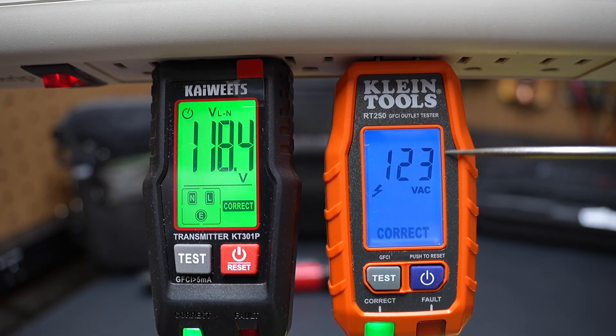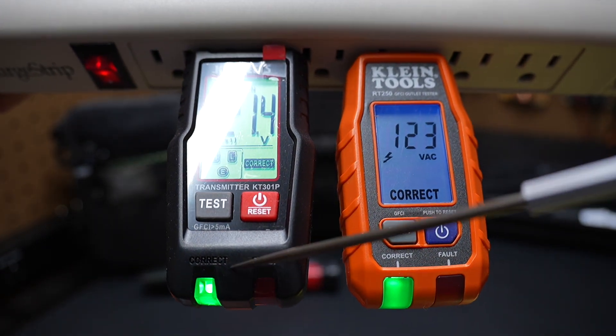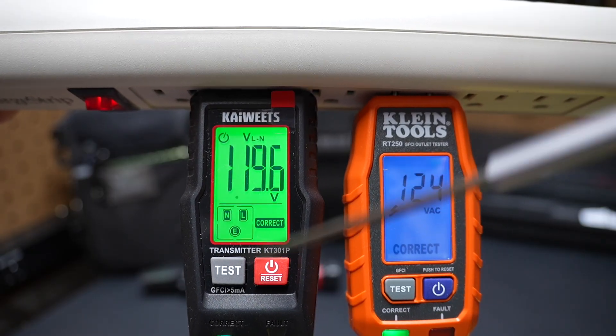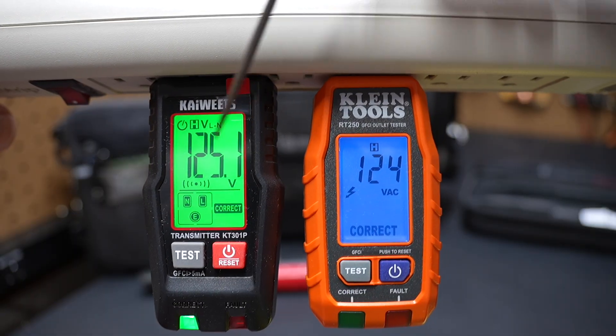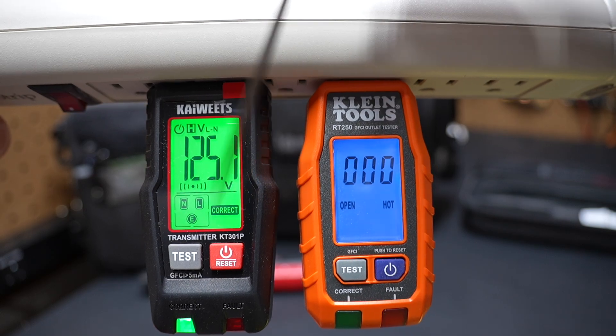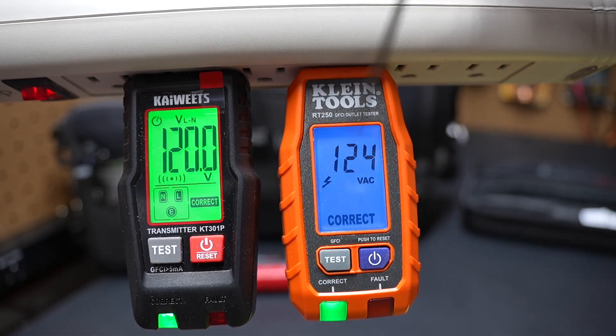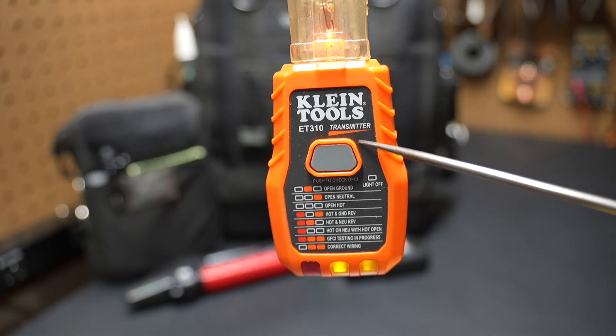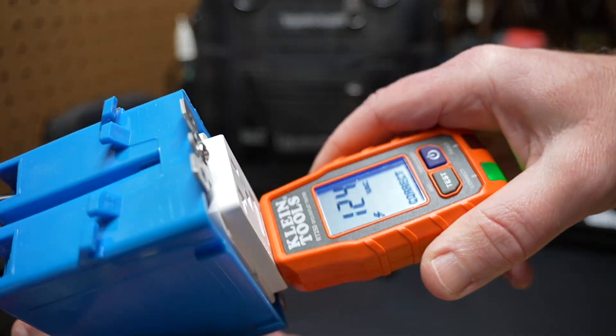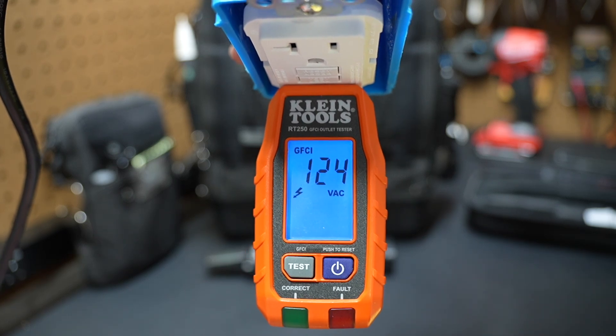Let's show the hold feature. I turn the power off and both the Kaiweets and Klein hold the reading. The difference is the Klein releases the hold after about 10 seconds and goes back to zero, while the Kaiweets holds until you plug it into another receptacle or hit reset. Turning the power back on, the Kaiweets starts reading again. For the GFCI comparison: on the Klein, plug in a GFCI receptacle, tap the test button, it trips the GFCI and gives you the trip time — 0.08 seconds — with the green light flashing.